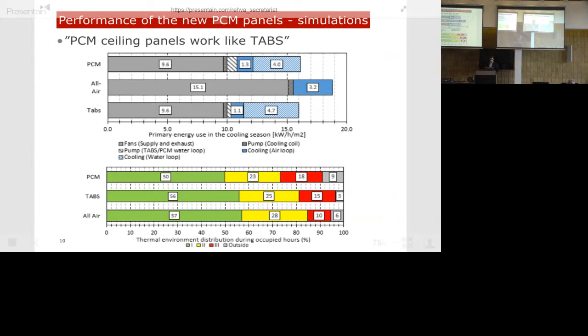The energy use of different components in the system is very similar between PCM and TABS. Also, though not shown here, the amount of heat removed by the ceiling surface in both PCM and TABS was very close—around 60 to 65% of the total heat removed from the room. In terms of the created indoor environment, they were also very close.